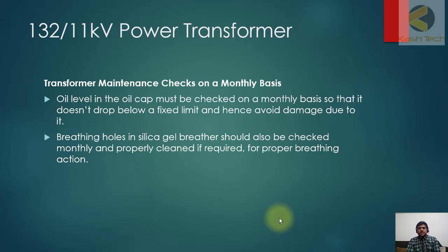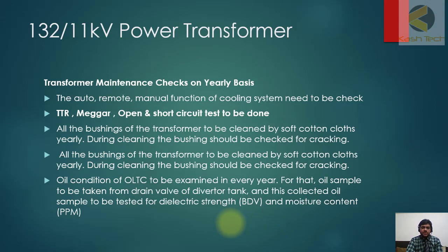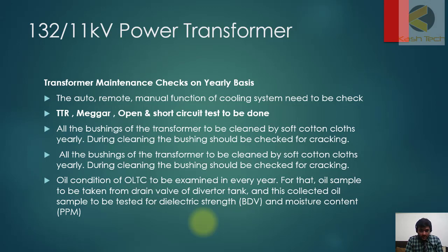The breathing hole in the silica gel breather should also be checked monthly and properly cleaned if required, to ensure proper breathing. It may happen that the transformer stops breathing because the breathing hole is choked, so look out for this issue as well. For yearly maintenance, the auto, remote, and manual functions of the cooling system need to be checked.